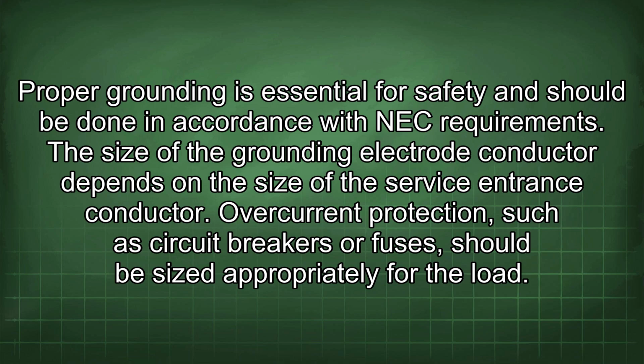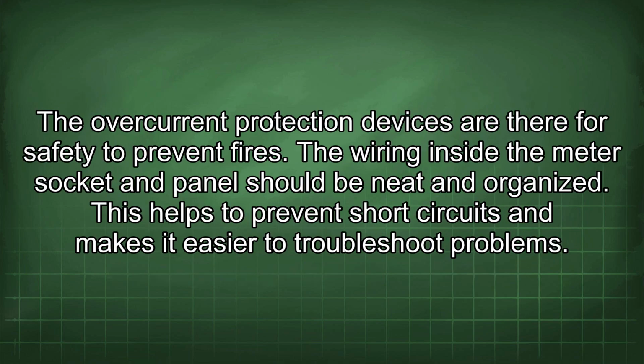Proper grounding is essential for safety and should be done in accordance with NEC requirements. The size of the grounding electrode conductor depends on the size of the service entrance conductor. Overcurrent protection, such as circuit breakers or fuses, should be sized appropriately for the load. The overcurrent protection devices are there for safety to prevent fires.